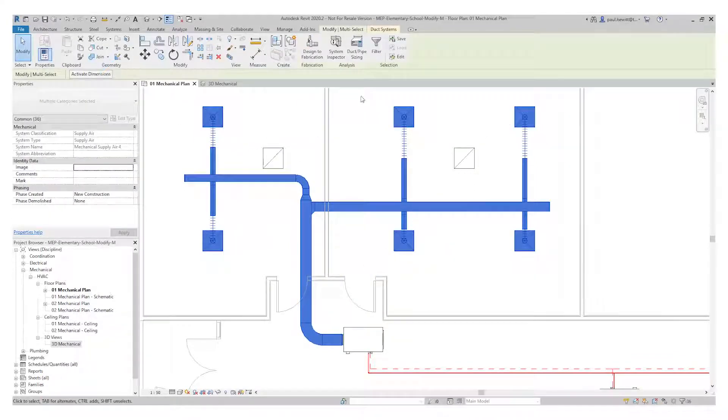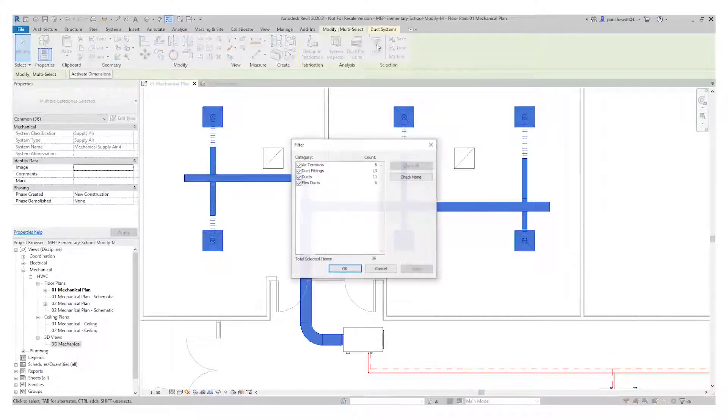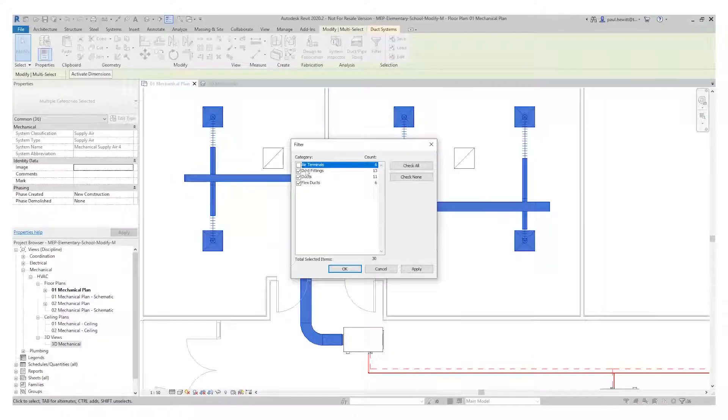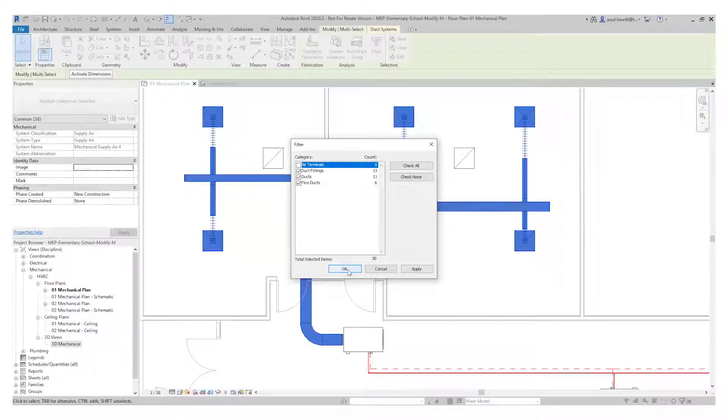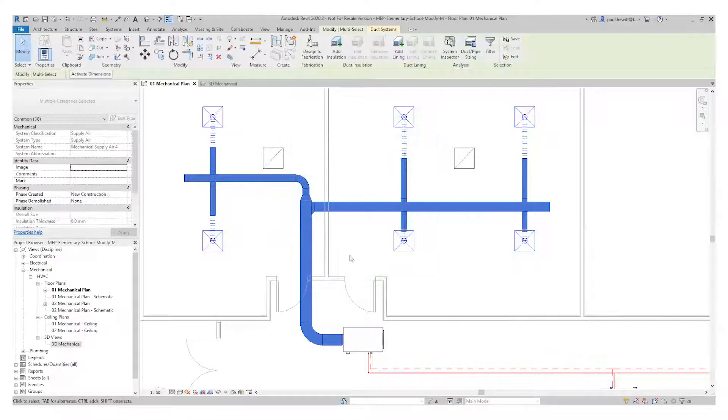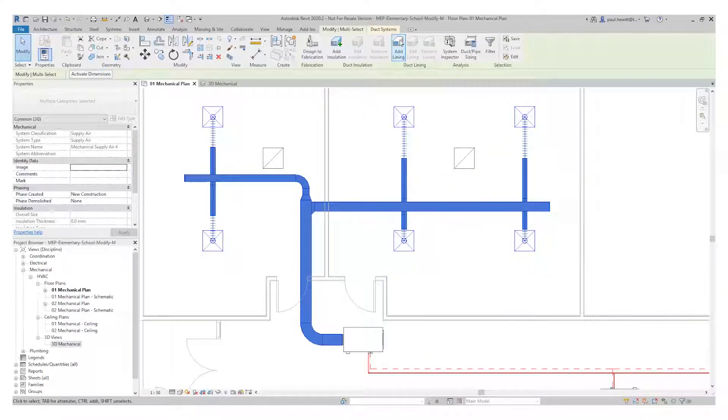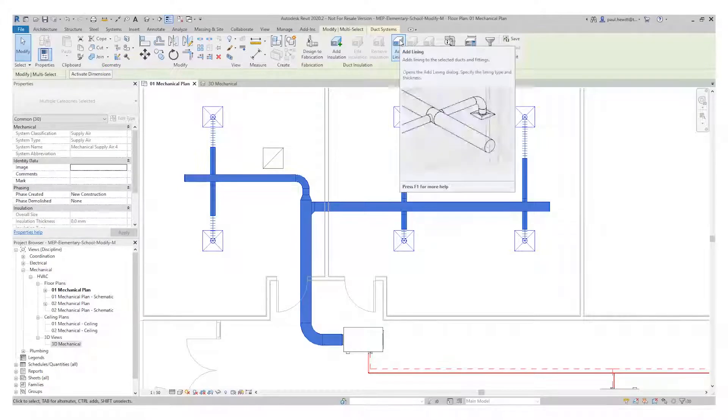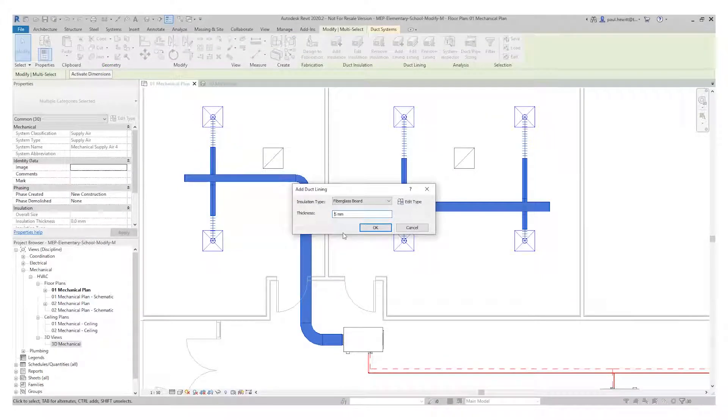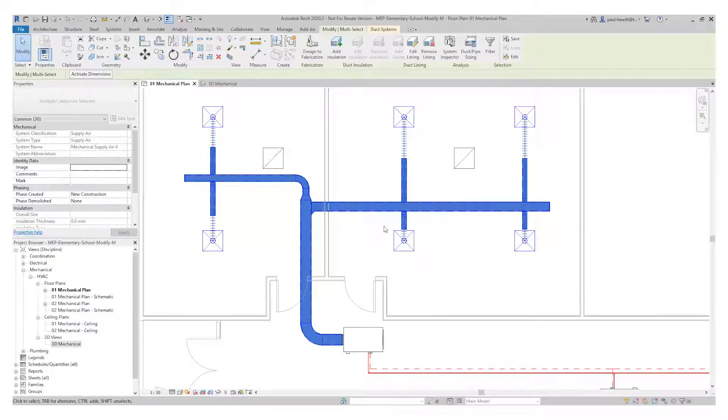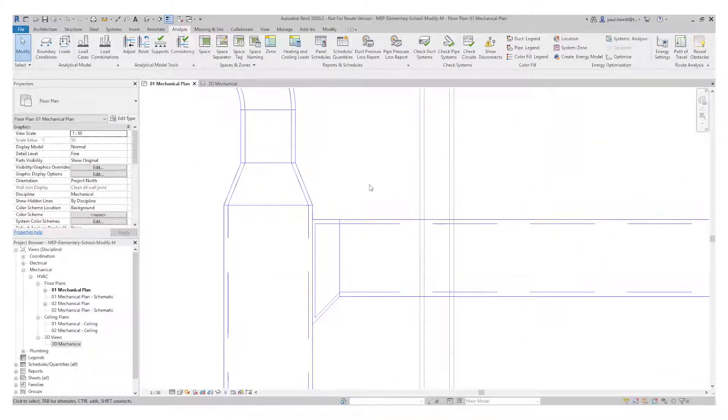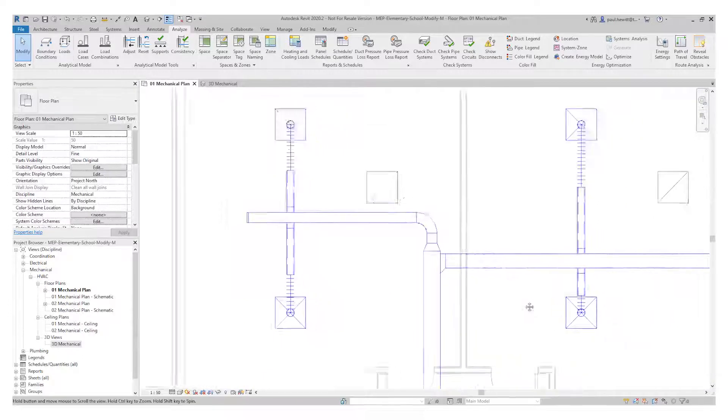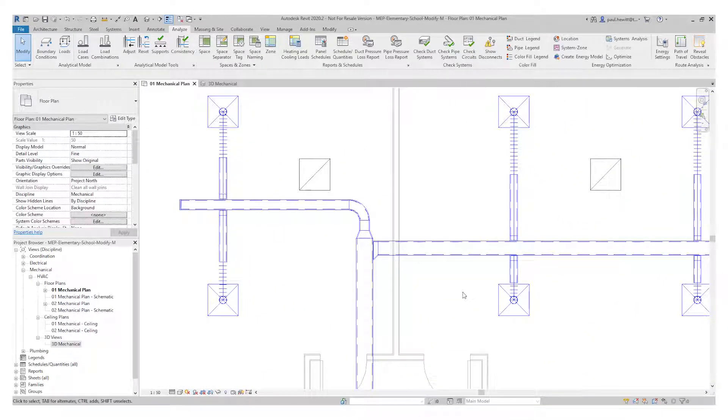Now all I need to do is I'm going to select this again using the tab option. And I'm going to add a lining here. But now I can't add lining if I've got something like air terminals selected. So I'm just going to use the filter and make sure I've only got the duct fittings, duct and flex duct. This will then allow me to go to add lining. And in the add lining I've got the option then to change the size. So I'm going to make this a 15mm thick lining. And OK. And if I deselect this now and we zoom in, you'll see we've actually got our lining added with our dotted line. So that's modifying ducts and pipes.